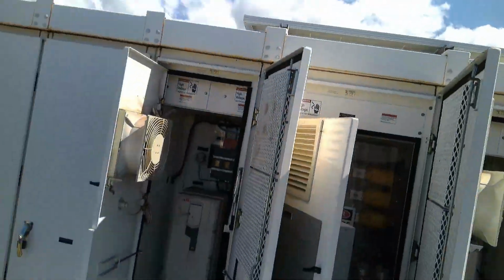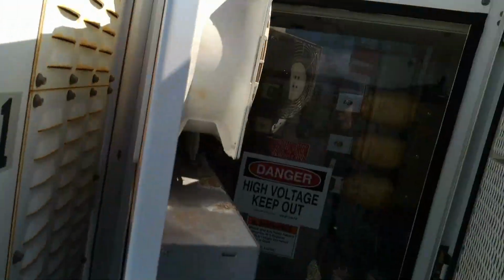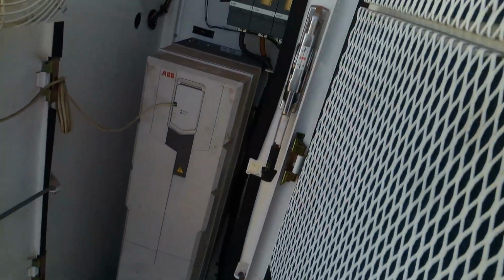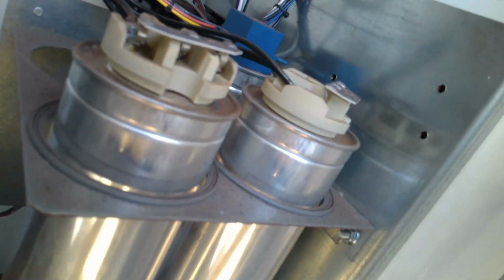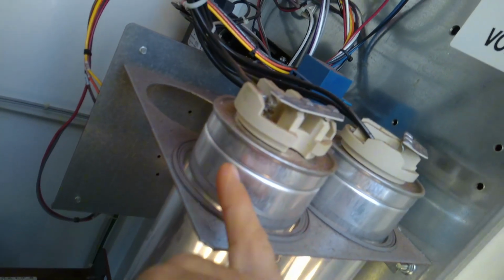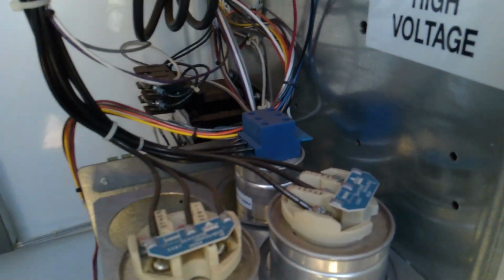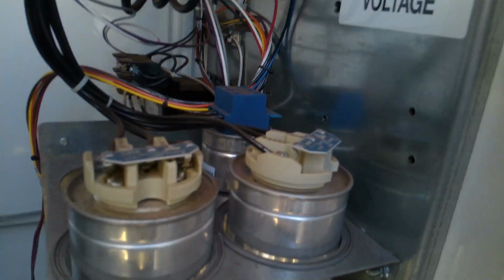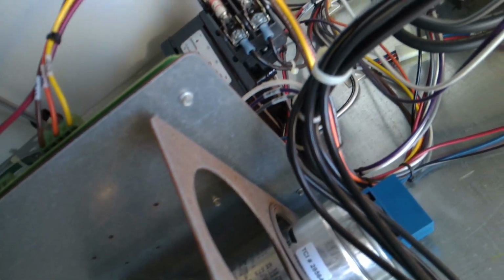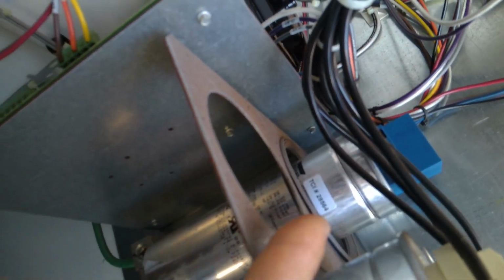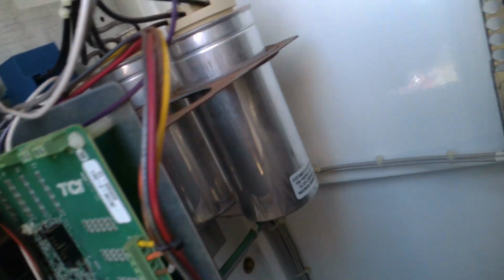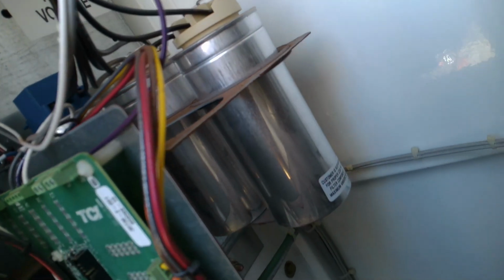P1 and P2. Capacitors inspected and pictures taken. That's in here. Visual inspection of capacitors. They have this expansion ring here for high pressure. They said to check that the terminals are all level. There's no bulging. That back one is a little bulged on one side. Not any more than the other one.